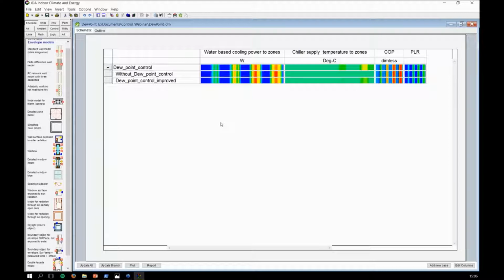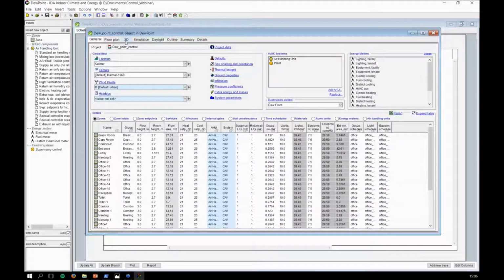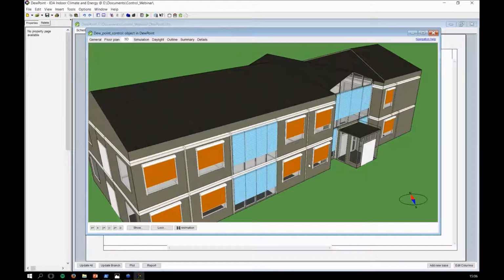But I also wanted to show two things. The first is that it actually reduces energy when you have a realistic chiller model. And that's where we're going to veer off, I think, a little bit and talk a little bit about fixed COP versus partial load curves. So here we have a dew point control, and I'll open the base case here. And again, we're going to use the same model all throughout this demonstration, that little office building that we have.